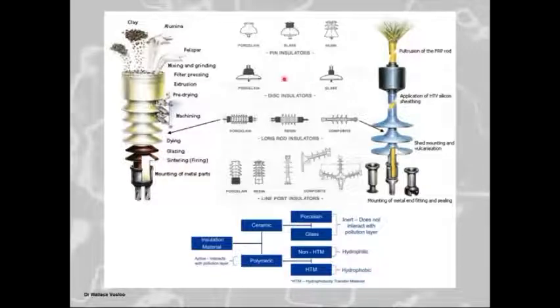So it depends on the type of end fittings which are used. Now, we also have long rod insulators, and they're normally made from porcelain. We also got the line posts and so on, but it's normally from porcelain or from composite. We have the resins like the cycloaliphatic resin. But to be quite honest, I don't really promote the resins too much, as we know they're prone to hydrolysis. But that's also a whole section on just materials which we can deal with if you want to later.